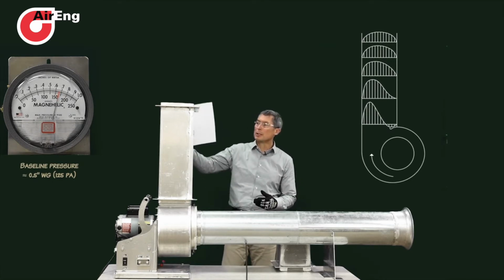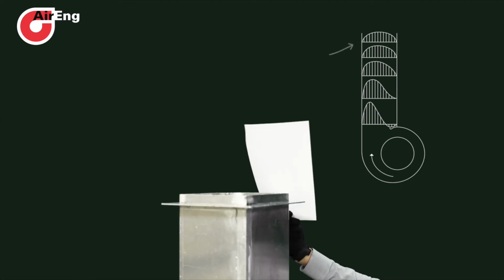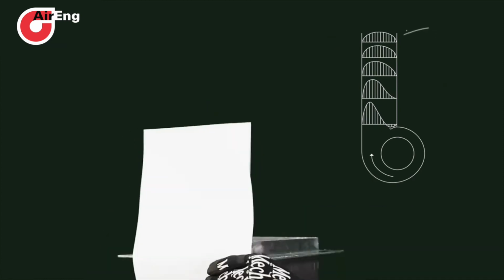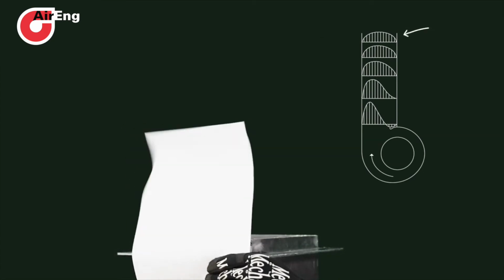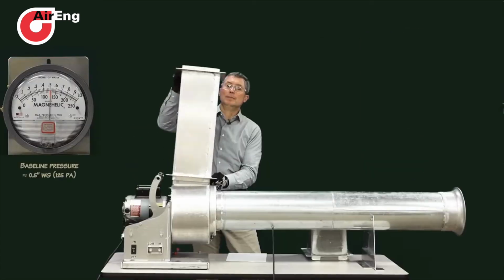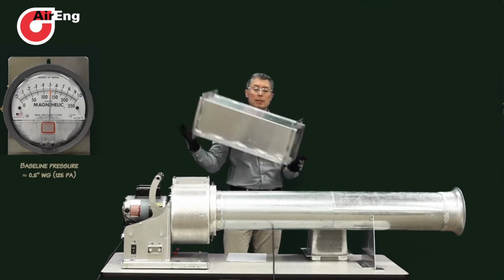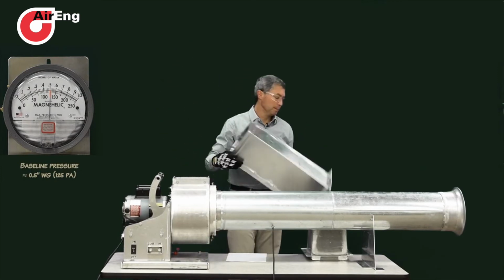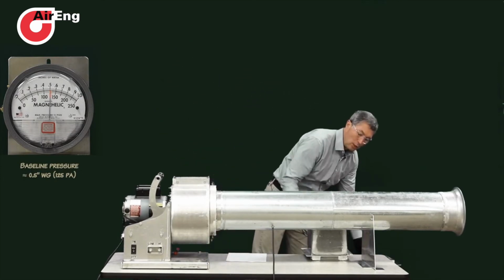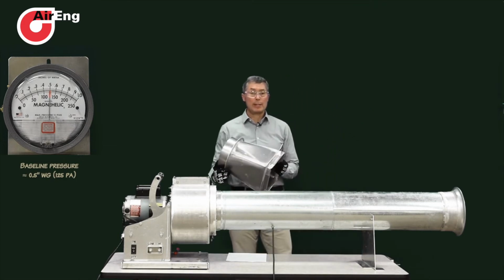Well, if I put this piece of paper on the outside of the volute shape, it still is forcibly stood up. However, if I put it on the inside of that volute shape, it's still forcibly pushed up. It's no longer being sucked into the fan just like it did behind the cutoff sheet. Now, you need a piece of ductwork, but how long do you need it? Well, even with a short piece of ductwork, you're going to get some regain.